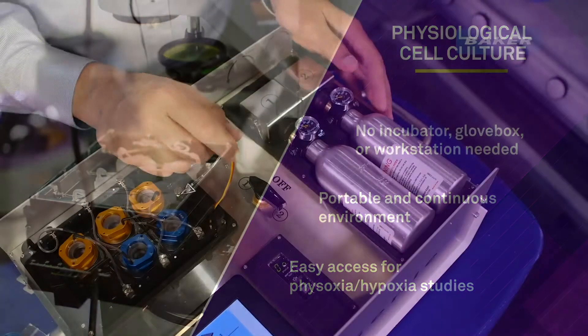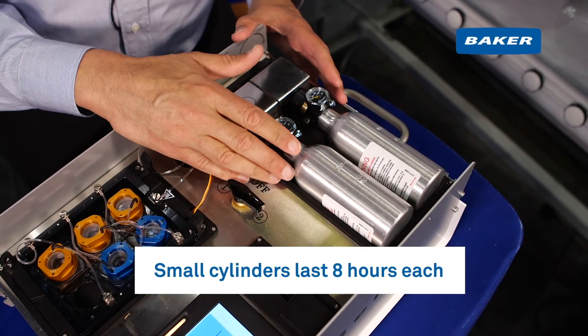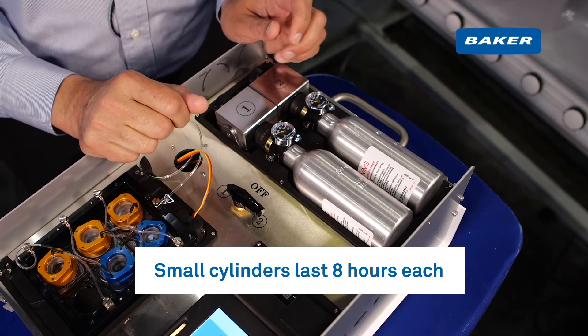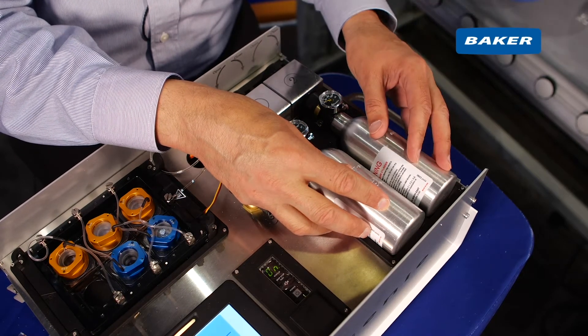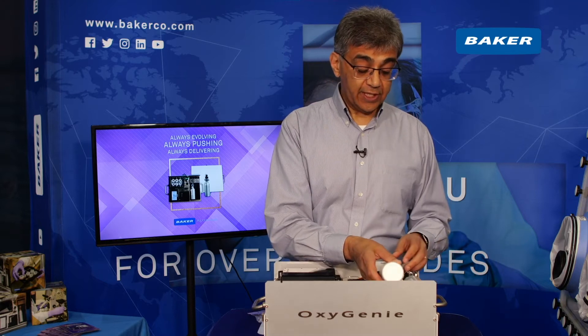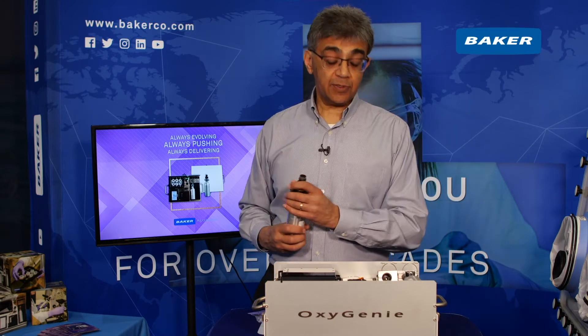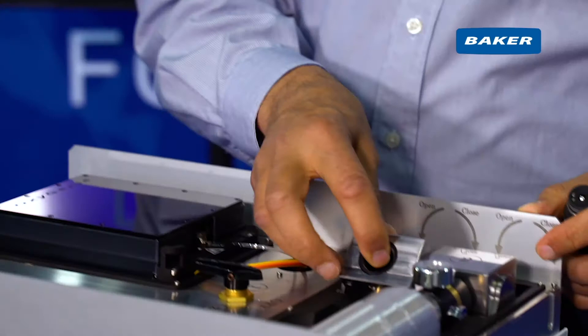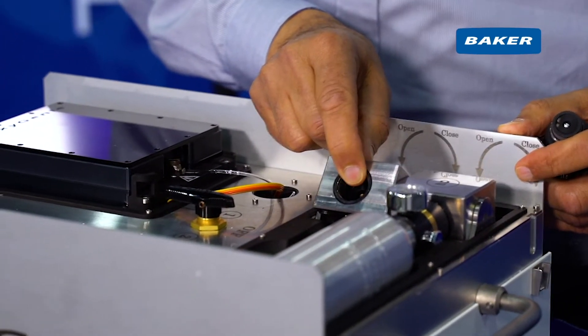On board the OxyGenie are two gas bottles. Each one will last eight hours. These can be filled with a pre-mixed gas, like 5% oxygen and nitrogen. Each cylinder can have a different gas, or you can have both of them filled with the same gas concentration. Alternatively, if you disconnect the gas bottle, you can connect a large laboratory gas cylinder directly into the OxyGenie using a special adapter.